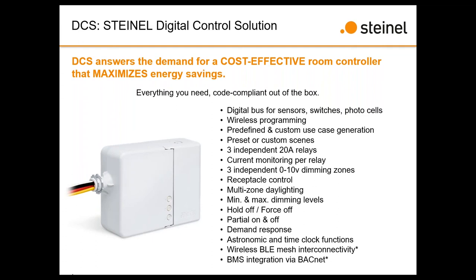This is a huge, huge benefit. In the standard device here, we have an input for an external time clock. So if there happens to already be a time clock in place, you can interface from it to our device. If you've got a master time clock out there, we've got a dry contact closure input. And we've also got an internal time clock. The internal time clock is set when you're commissioning the device. We take the location of the commissioning tool. So you've got the phone, and the phone's location will download the correct set of astronomic tables, and we'll upload those into the device during commissioning. So now you have astronomic and regular internal time clock functions built into the device.